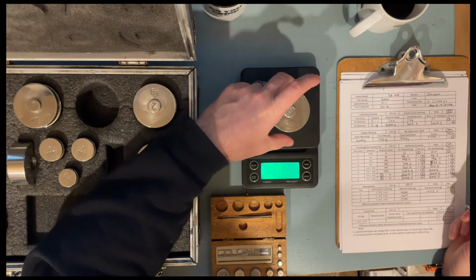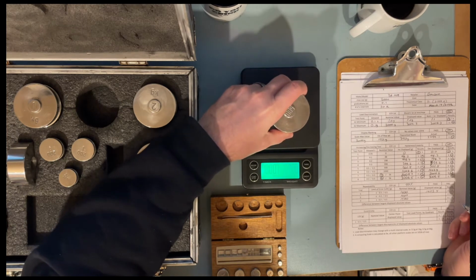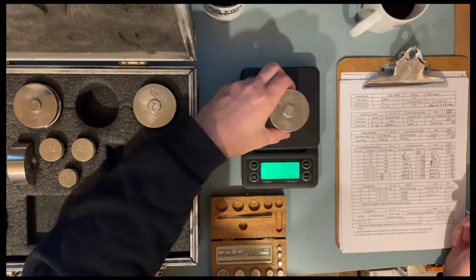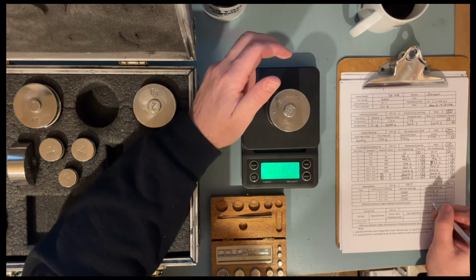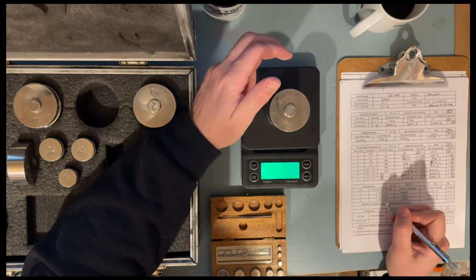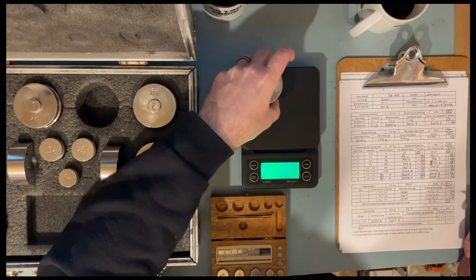This next test is called repeatability. We take a load that is equivalent to half of the maximum weight of the scale, we place it in the same location, the same way, and we record the value. After 3 weighments, the values must be within the limit of error. For repeatability, this scale passes. It still fails in performance because 3 grams is outside of the 0.3 grams that is allowed.